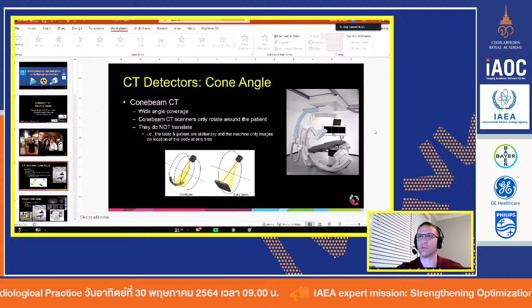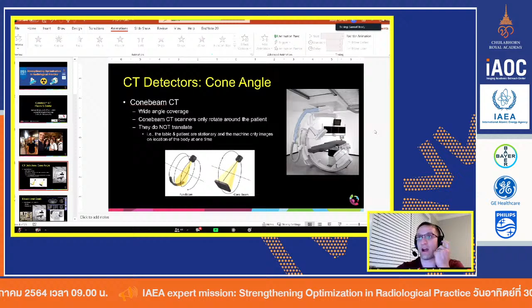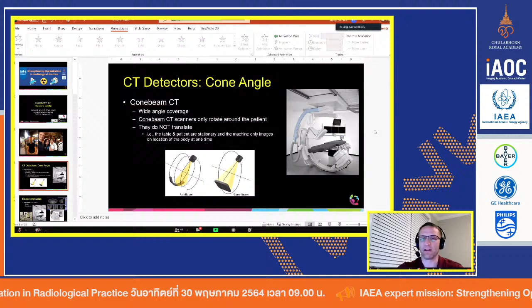No, the machine is fine. Yes, you are acquiring more images, but the X-ray tubes in a C-arm fluoroscopy system are actively cooled, and you may use them for interventional procedures for 2 or 3 hours. So if you do one CBCT, it's not that big a deal. If you did 100 CBCTs, maybe, but no one's ever going to do that. These systems are very good at keeping the heat down, so no, you shouldn't have to worry about that.